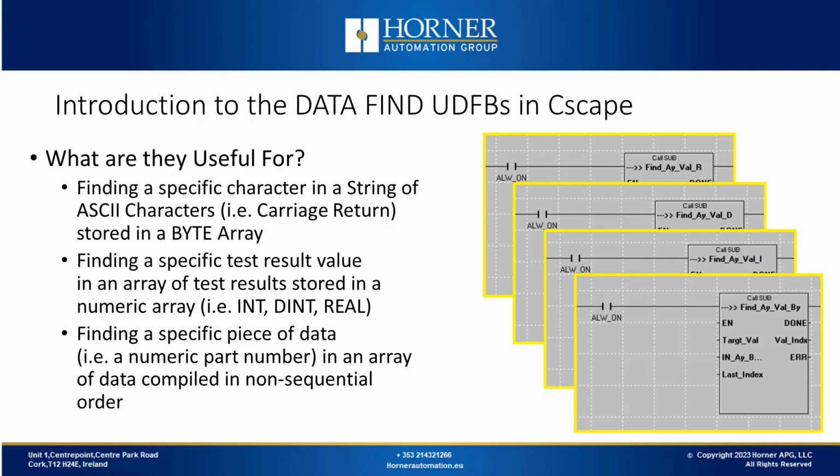Another use might be for those of you who utilize data logging or other type functions in Cscape, where you're recording the test results in your machine. If you're recording temperatures or pressures and there's a specific pressure value that you know you're looking for, but you don't know exactly where that pressure test result occurred, you could search for that value. And this function block would come back and show you specifically which test it was where that was the result you received.